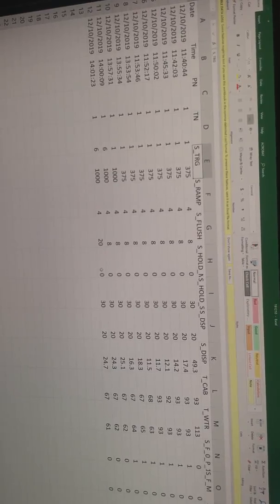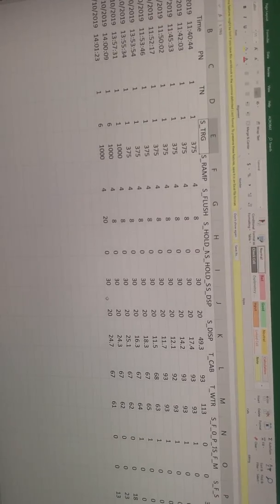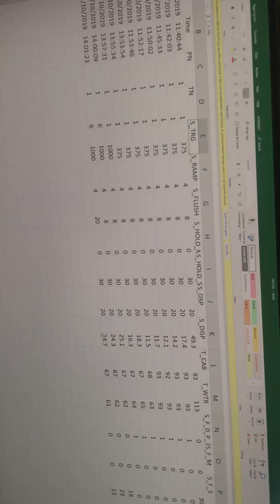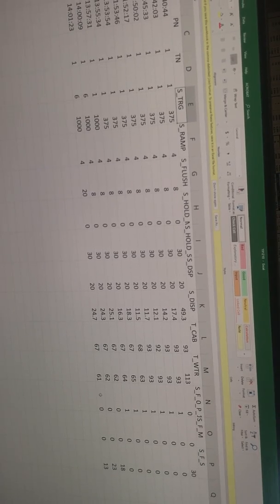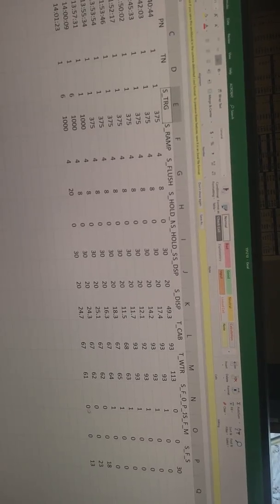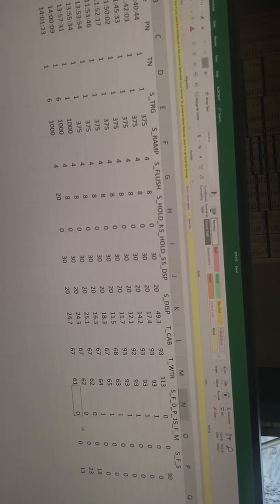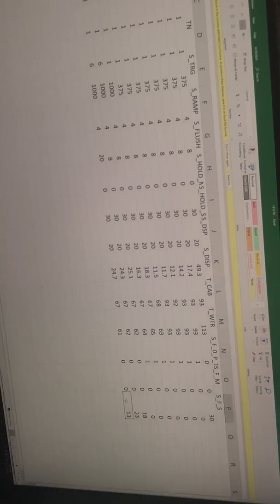Sorry, this was a static test. The time was 0 minutes, 30 seconds, so we ran it 30 seconds. And then we said 20 cc's was our trigger. This thing actually recorded a maximum of 24. And these were your temperatures in the cabinet and the water. And then this is cryptic here, but static fail is 0 and pass is a 1. So here's a 0. That means it's a failure. And it did it at 0 minutes, 13 seconds into it. Cool. And so every time you run another test, it's going to append another row.